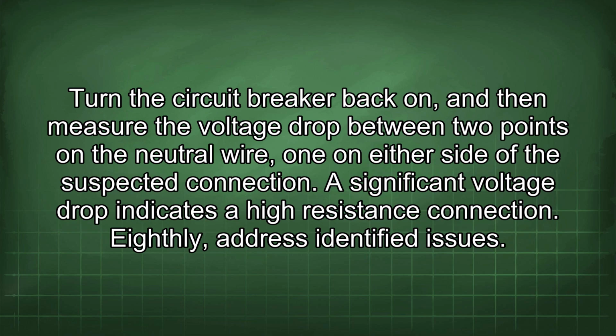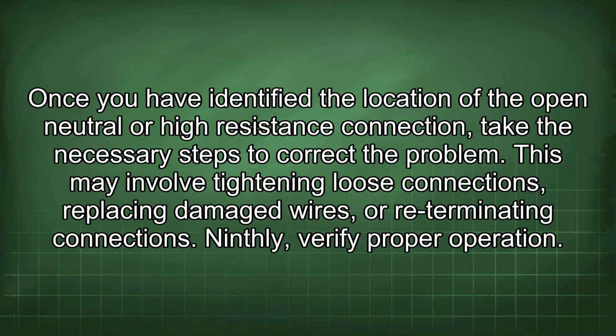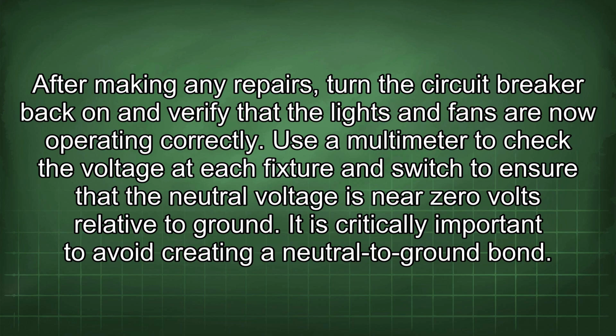Eighthly, address identified issues. Once you have identified the location of the open neutral or high resistance connection, take the necessary steps to correct the problem. This may involve tightening loose connections, replacing damaged wires, or re-terminating connections. Ninthly, verify proper operation. After making any repairs, turn the circuit breaker back on and verify that the lights and fans are now operating correctly. Use a multimeter to check the voltage at each fixture and switch to ensure that the neutral voltage is near 0 volts relative to ground.